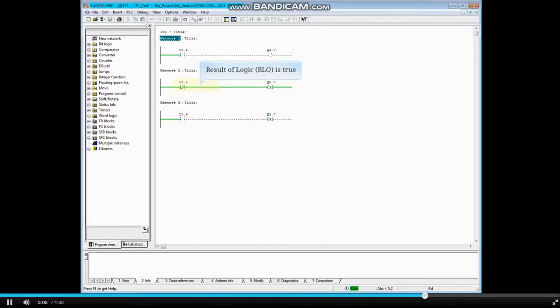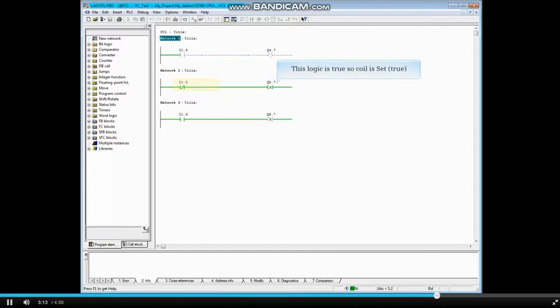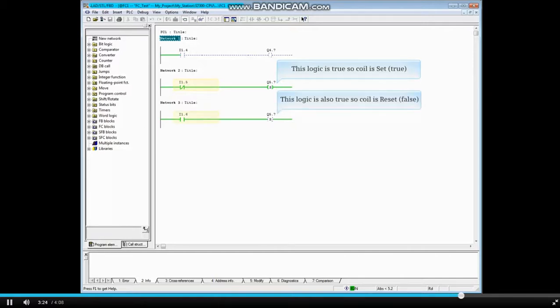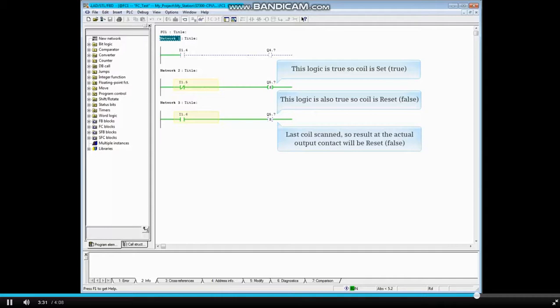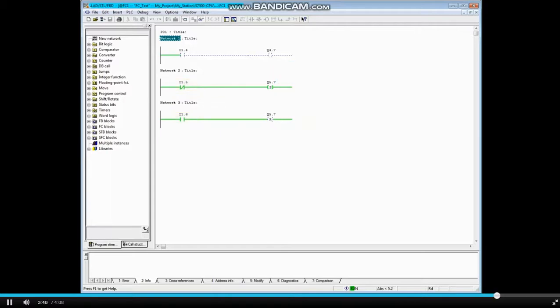The result of the logic in network 2 is true again, therefore the coil is set. When the logic in network 2 goes true, coil Q 4.7 is set or true. When the logic in network 3 goes true, the coil is reset or false. If the logic in both networks remains true, then network 3 — the last one scanned — writes the logic to output coil Q 4.7, which will be false.